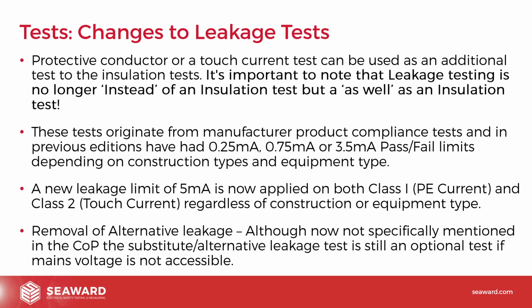So the way it's specified now in the 5th edition is that you must do an insulation test. And then if you've done an insulation test, you can then do a leakage test as an additional test. What we can't do is a leakage test on its own. We must do an insulation resistance test before we carry out a leakage test. So just be aware of that difference. Before it was either or: you could do a leakage test or an insulation test. Now you must do an insulation test and you can also add a leakage test as well, should you need to. It's a slight difference, and I'll talk about the flowchart in a moment.